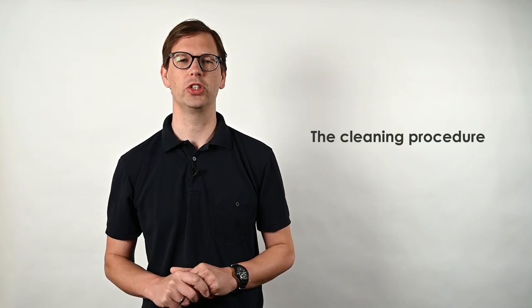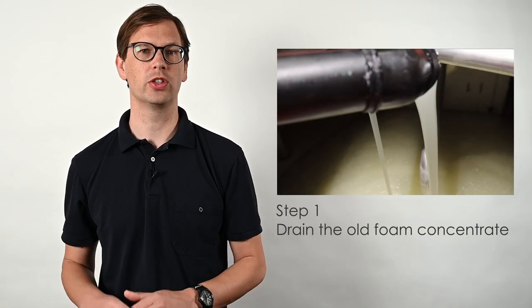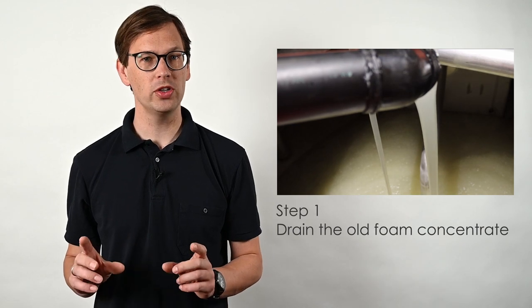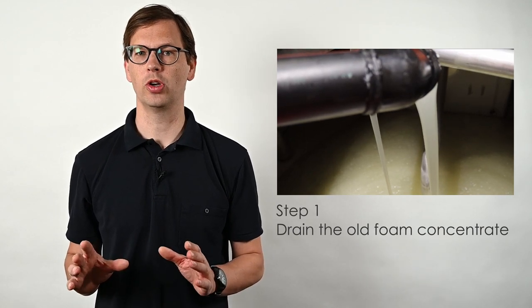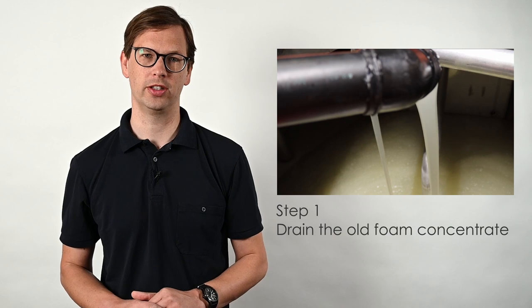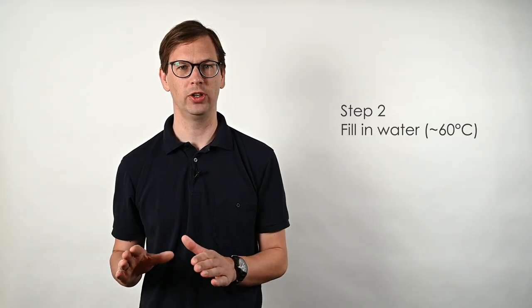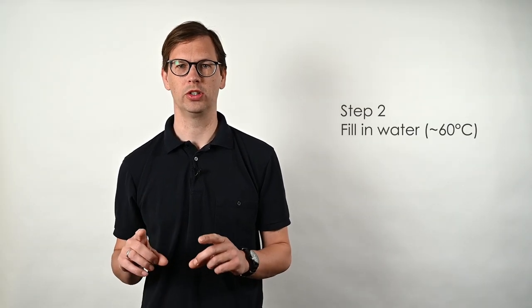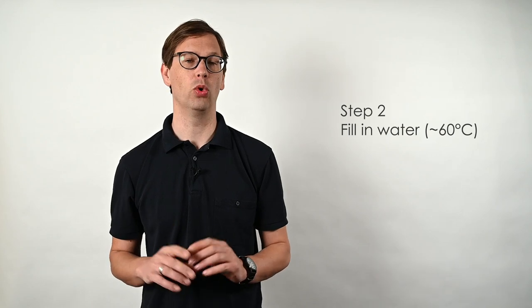Here is the cleaning procedure. First, you drain the old foam concentrate from the tank, and because it contains PFAS, you dispose of that foam through high temperature incineration. In the second step, you fill in water. Use warm water because the concentrate dissolves better in warm water. About 60 degrees Celsius should do.